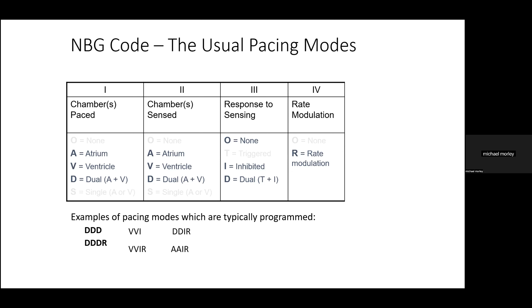So the pacing modes describe how the pacemaker is going to behave. The first letter is the chamber which is paced. The second letter relates to the chamber or chambers which can be sensed by the pacing system. And the third letter describes how the pacemaker responds to a sensed event. And I'll show you some examples of this in a second. The fourth letter, which is sometimes added on, which is R, so people might talk about DDDR pacemakers, relates to the fact that modern pacemakers have rate modulation. They're able to detect intrinsic activity of the patient and speed up and slow down the heart rate to try and mimic normal physiological changes in heart rate.